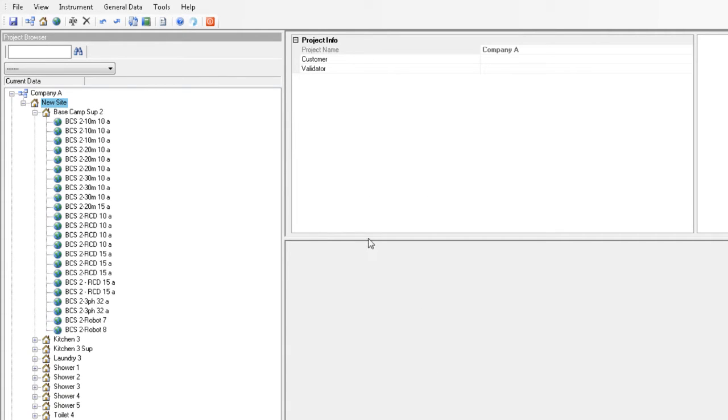With the reading measurements, the basics that I always set up for people is instrument name is always DeltaPAT. I always untick the auto detect box, and the COM port you manually choose. Now this is usually where things get stuck. COM1 is always the serial port on your computer, so it's never COM1. It's usually COM3, COM4, COM5, something like that.